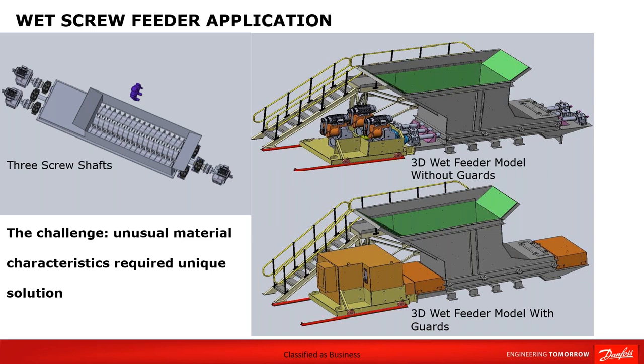And it was for this reason that 22 kilowatt drives with 22 kilowatt motors were put forward, and this has now proven to be especially true during start conditions or low, what we call low feed rate conditions.